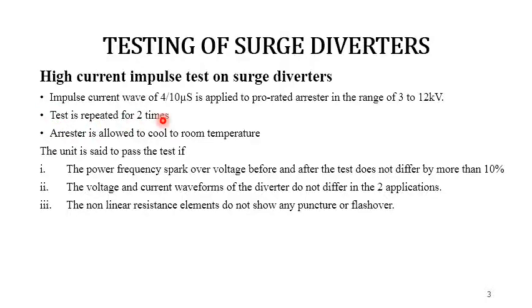This test is repeated two times. That is nothing but two such applications are made on the units under test, which allows sufficient time for the cooling of the unit to room temperature. The unit is then said to pass the test if the power frequency spark-over voltage before and after the test does not differ by more than 10%, the voltage and current waveforms of the diverter do not differ in the two applications, and the nonlinear resistance elements do not show any puncture or flashover.